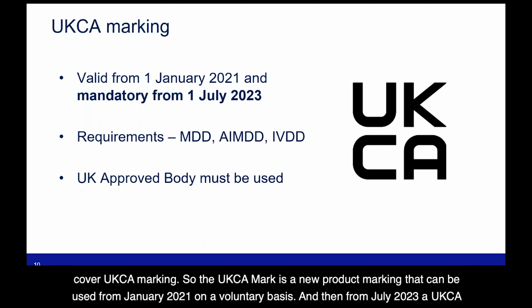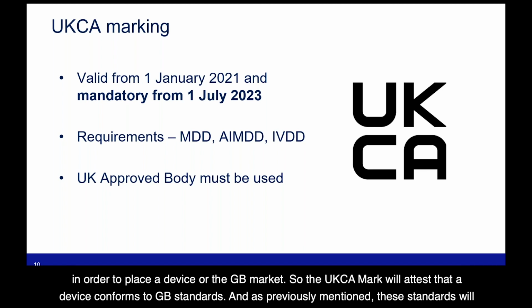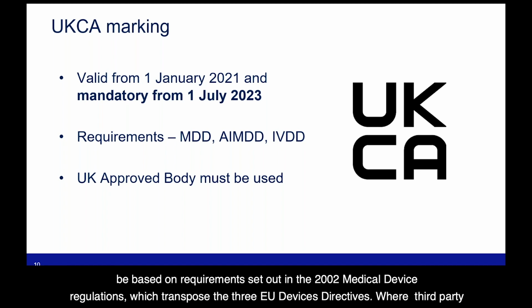Okay, so next I'll cover UKCA marking. The UKCA mark is a new product marking that can be used from January 2021 on a voluntary basis. And then from July 2023, a UKCA mark will be required in order to place a device on the GB market. So the UKCA mark will attest that a device conforms to GB standards. And as previously mentioned, these standards will be based on requirements set out in the 2002 Medical Device Regulations, which transpose the 3 EU devices directives.